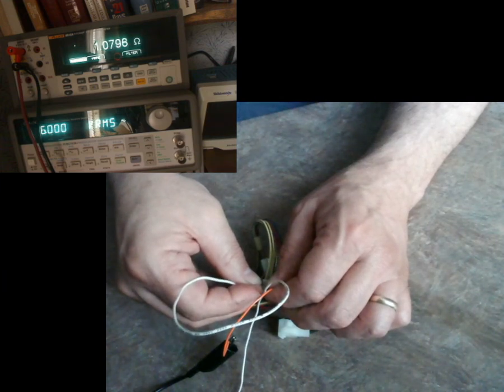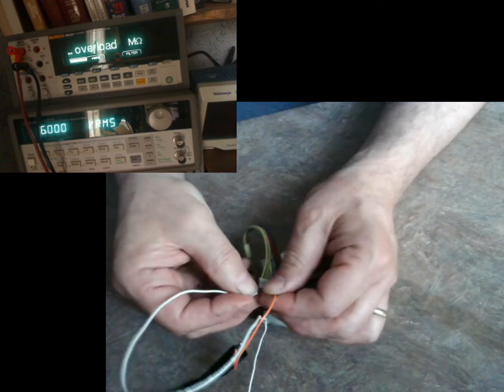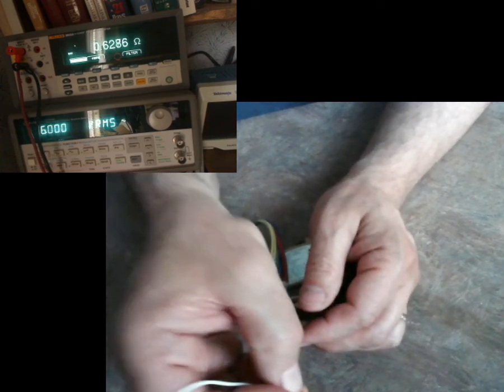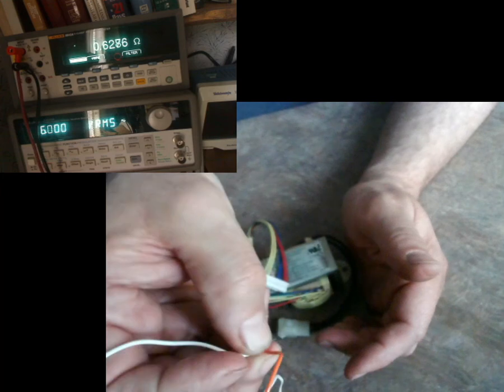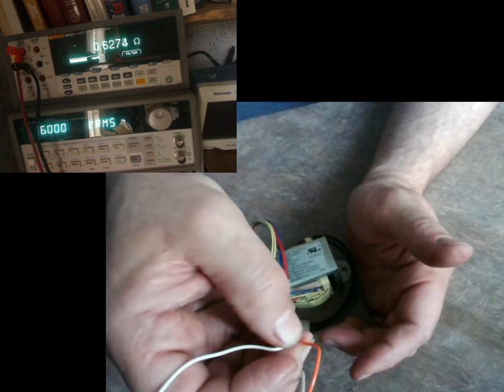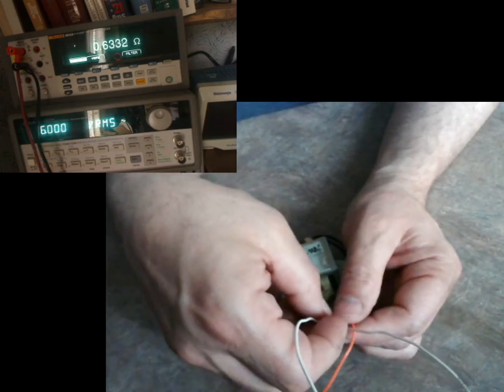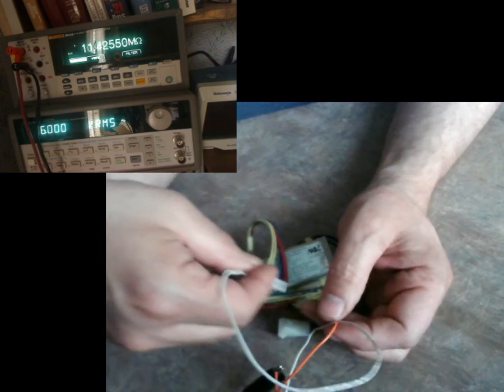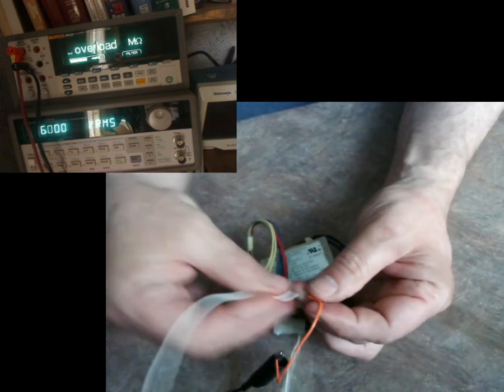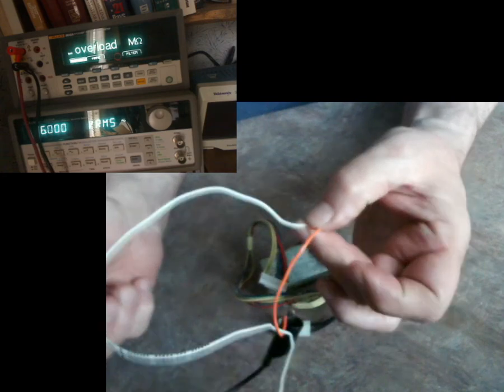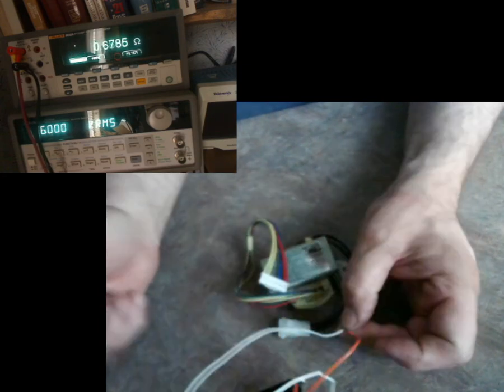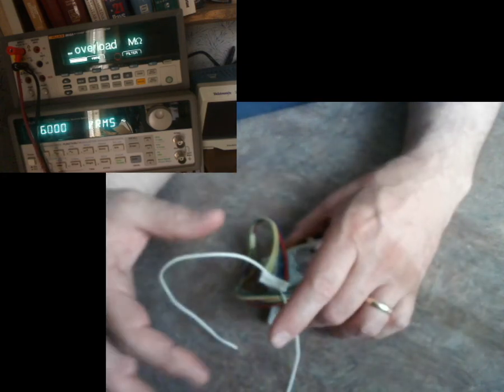But if I were to just short these two out, well, it's reading 0.62 with them just shorted out. So we're definitely reading more than just the resistance in my lead wires. So hopefully this is good.